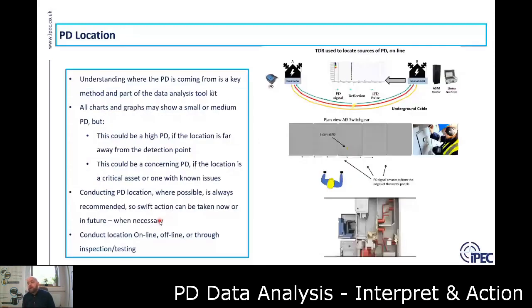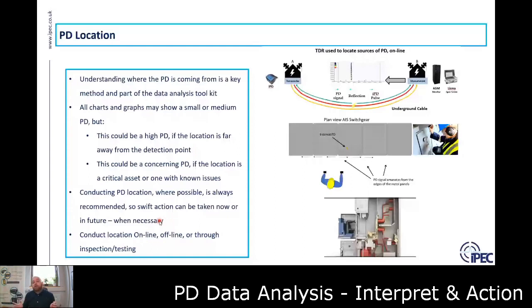The next step is PD location. Many people think you only conduct PD location when you're ready to repair, but that is not the IPEC philosophy. We recommend locating PD whenever you can. Unless we know the PD location, we don't know how far that signal has traveled to reach the sensor, so we don't know how attenuated it is. We also don't know what asset the PD is coming from — for example, corona ionizing the air is not very concerning, but contamination on a bushing or insulator on a critical component could be very concerning even at a lower level. So we recommend locating all PDs so you can take swift action, if not now, then in the future.